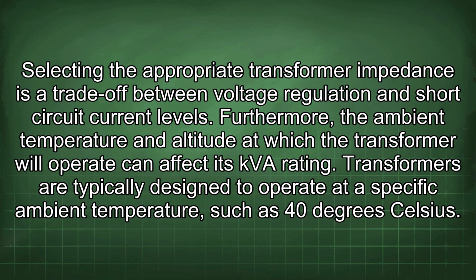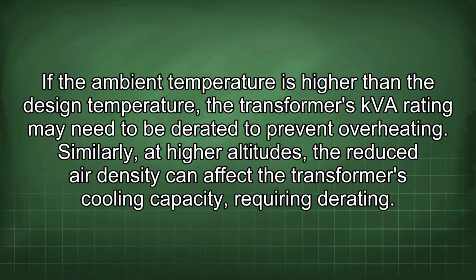Furthermore, the ambient temperature and altitude at which the transformer will operate can affect its kVA rating. Transformers are typically designed to operate at a specific ambient temperature, such as 40 degrees Celsius. If the ambient temperature is higher than the design temperature, a transformer's kVA rating may need to be derated to prevent overheating. Similarly, at higher altitudes, the reduced air density can affect the transformer's cooling capacity, requiring derating.